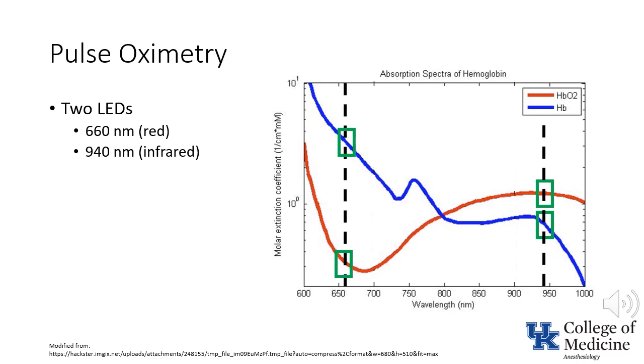Based on the differential absorptions of light, it is possible to estimate the amount of oxyhemoglobin and reduced hemoglobin, which in turn allows calculation of the approximate percentage of hemoglobin that is oxygenated, or the functional saturation.